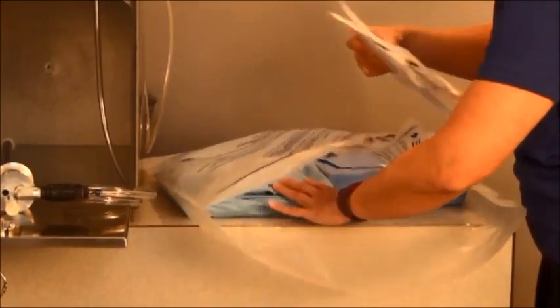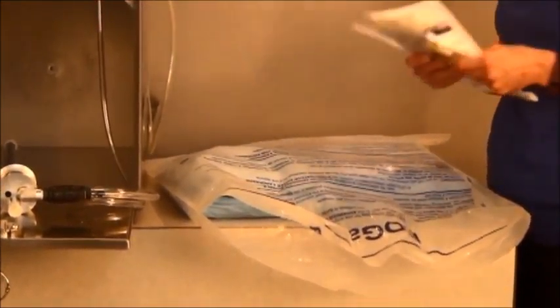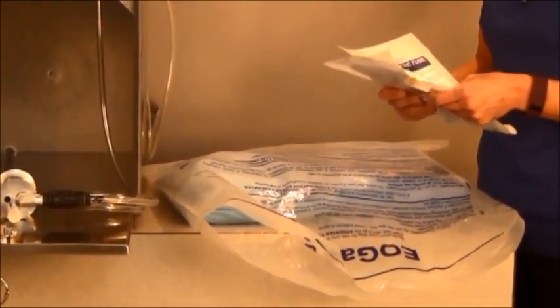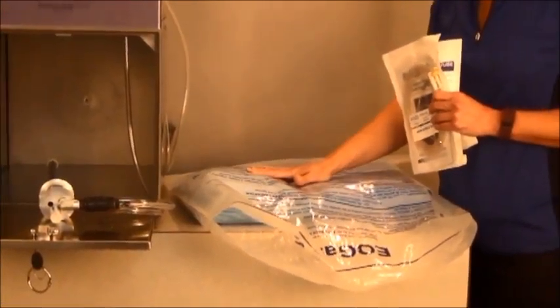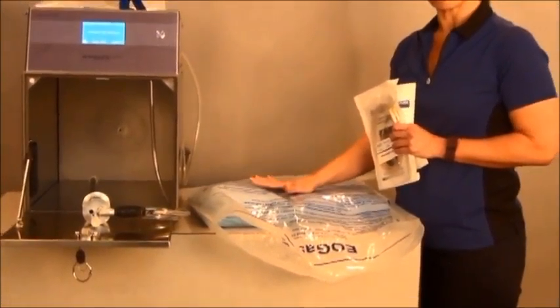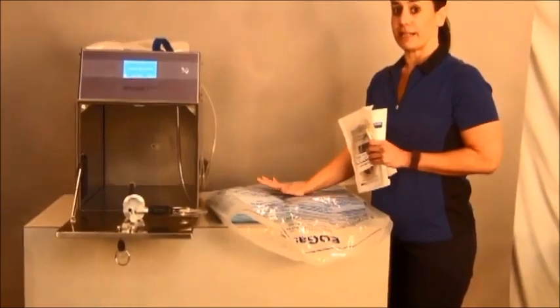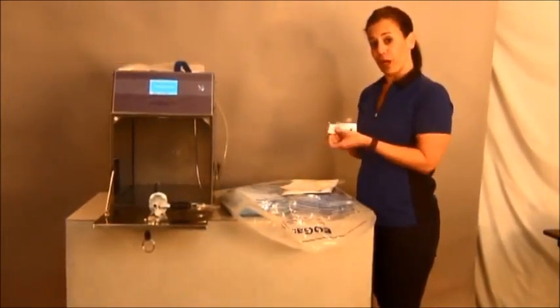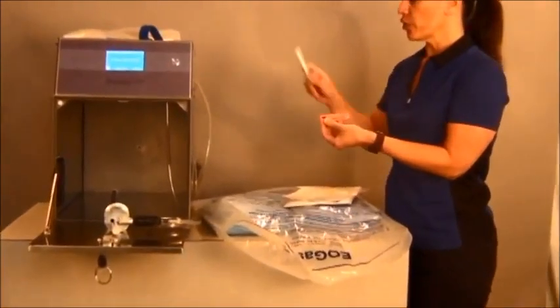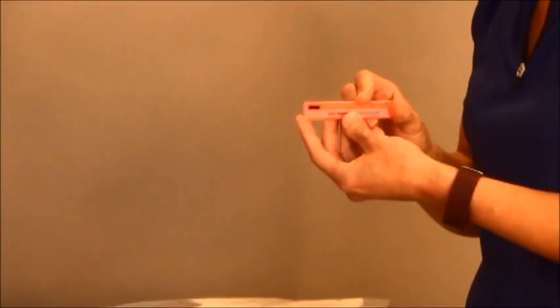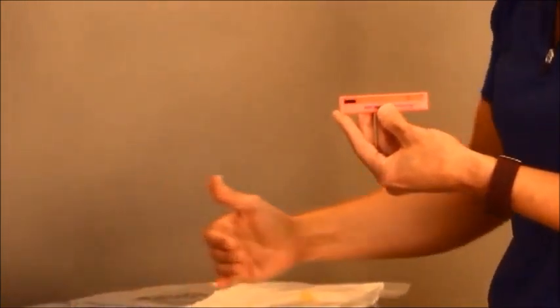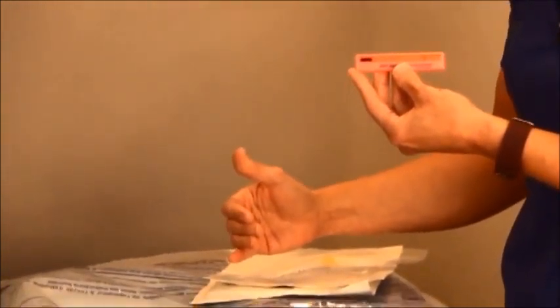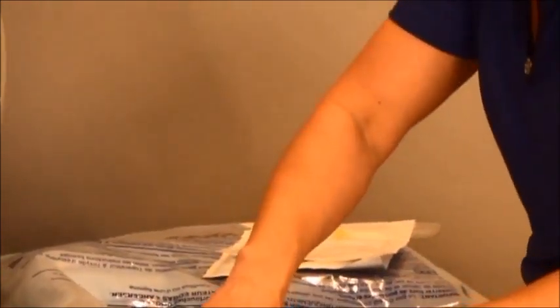At this point in time, I still have 2 items left to put into the liner bag. So I'm going to make the addition of my dosimeter, which is my chemical indicator. I remove it from its foil pouch and I place it into the liner bag into the least accessible portion for the gas to reach. So you want to place it between the items that you're going to be sterilizing.